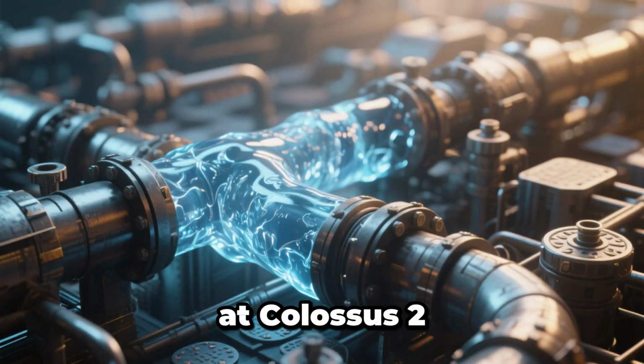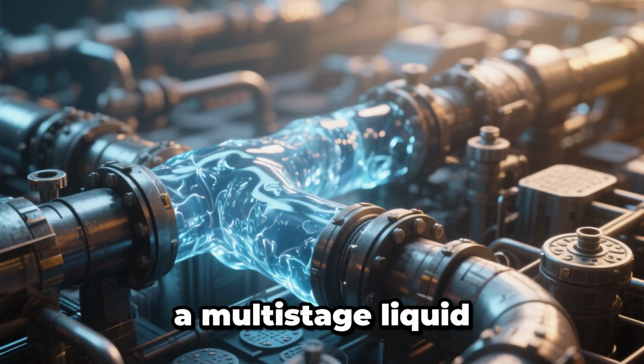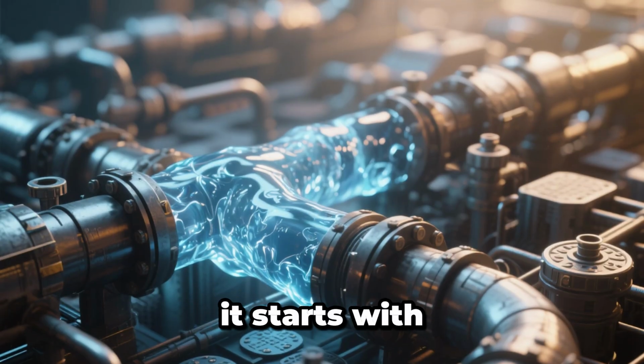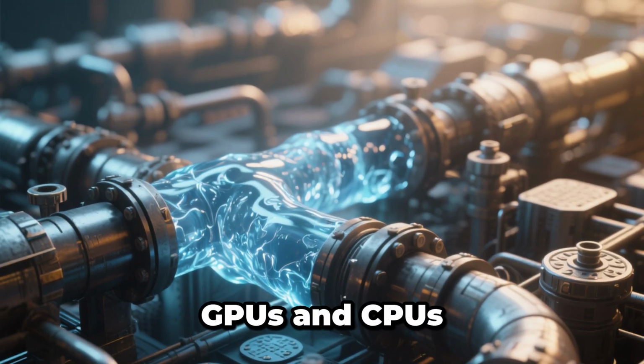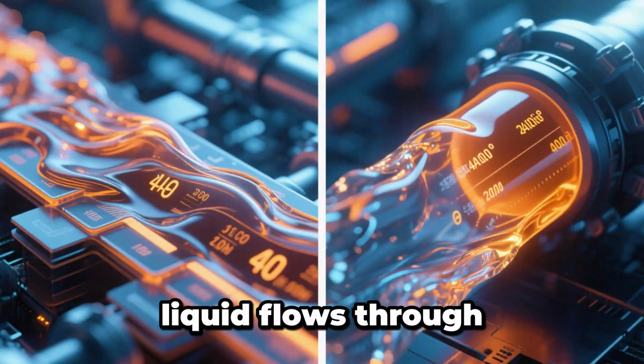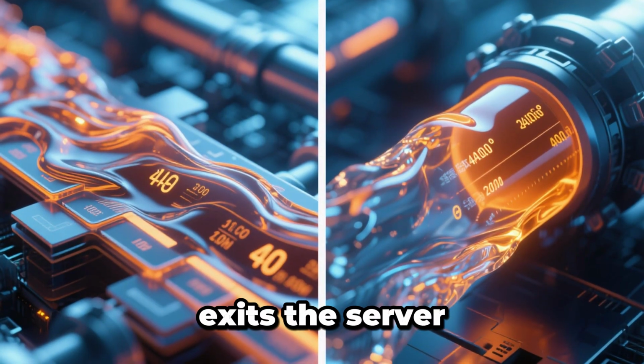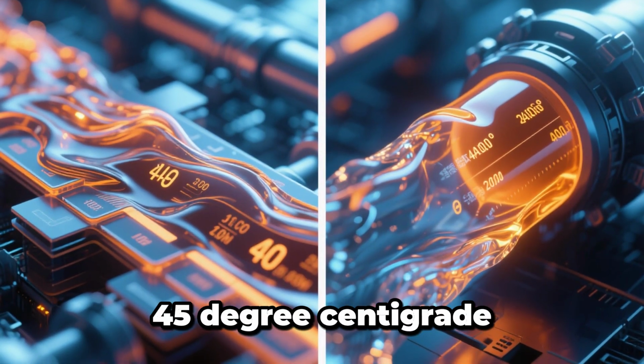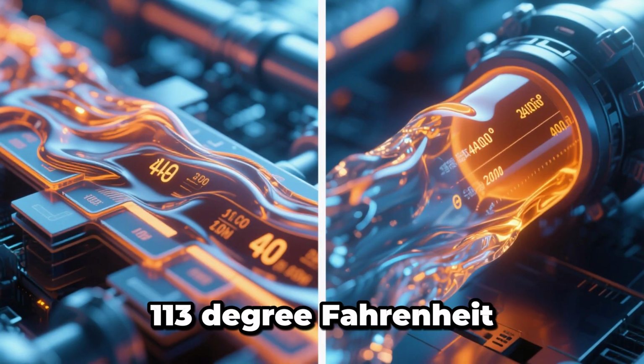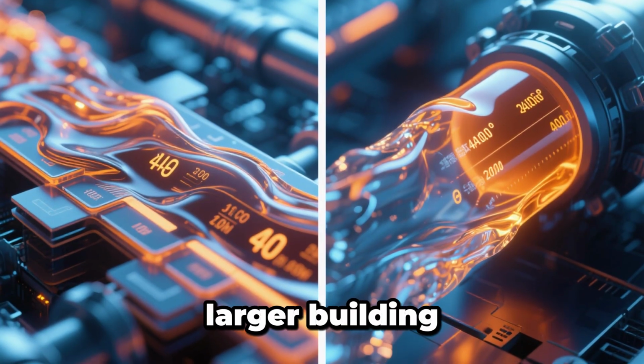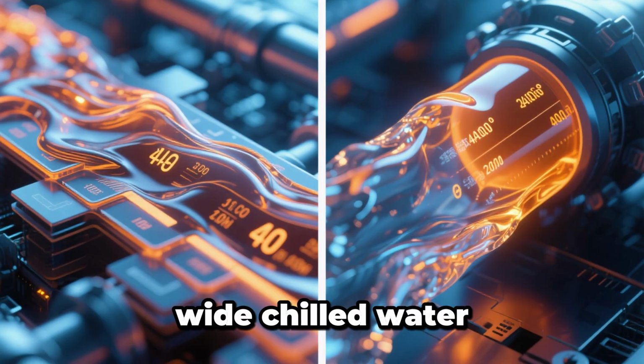At Colossus 2, the solution is a multi-stage liquid pipeline. It starts with cold plates mounted directly on the GPUs and CPUs. Liquid flows through these plates, exits the server racks at 45 degrees centigrade, 113 degrees Fahrenheit, and transfers its heat into a larger, building-wide chilled water network.